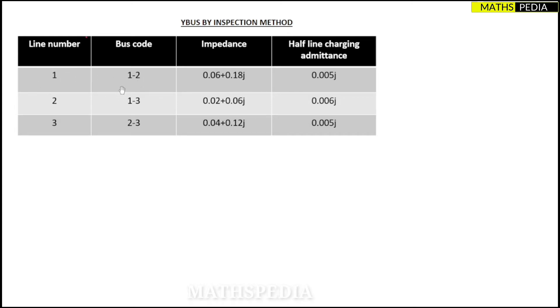We have connections: one to two, one to three, two to three. The maximum bus number is three, so total buses is three. The Y-bus matrix will be n×n — number of nodes times number of nodes — giving a 3×3 matrix. It is always a square matrix; if maximum buses are four, it will be 4×4.